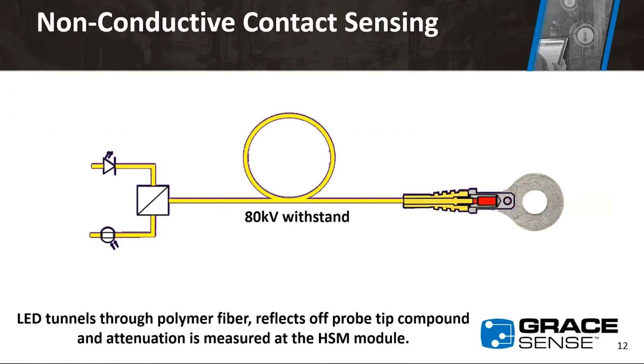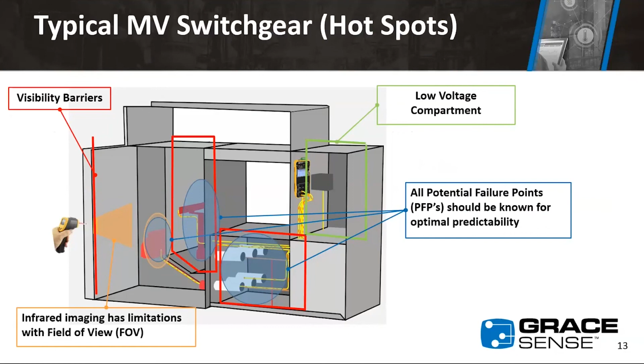Here's an example of why you'd want something like this outside of just 24/7 monitoring. From the left, you have your IR window, and you can see some connections, but not everything, because it's behind guarding or there's just not enough view from the window. So this can cover those connections you can't see, to either complement or potentially replace IR in that piece of equipment.